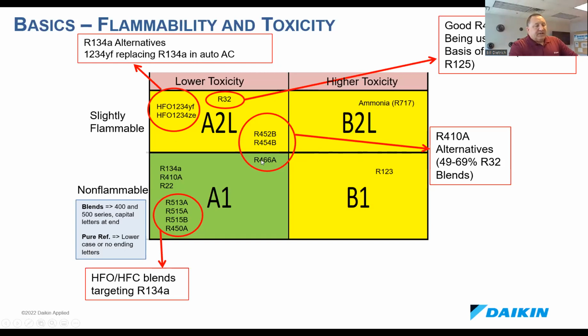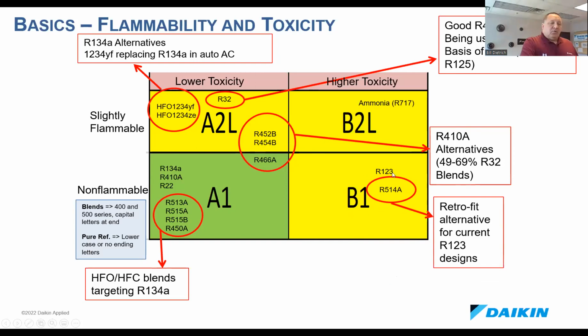And then there's another interesting blend that Honeywell introduced called 466A. What's interesting about this is it's a potential 410A alternative that falls into the green box. The big issue is there's iodine in there, and there are a lot of chemical and material stability and compatibility concerns that people are working on right now. When we get over to the B1 box, there's another refrigerant, R514A, that was really engineered to be similar to R123. So the same low pressure, slightly less capacity, but it could work in a new 123 machine and could be retrofit into an existing 123 machine.